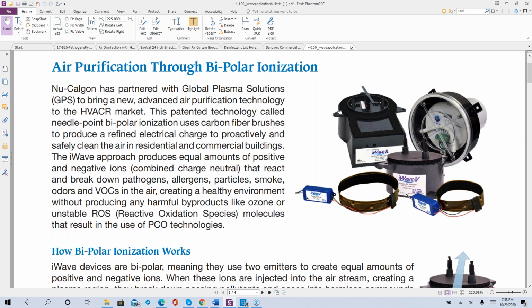What we want to do is we'll take a 24 volt transformer and put it to the load side of the fan contactor to power the 24 volts. At 10 or 12 VA, typically your control transformers are only 40 VA, and you're going to get pretty close to the capacity, and you'll start chattering relays and not producing the proper amount of ions. So that's why we don't use the control transformer.